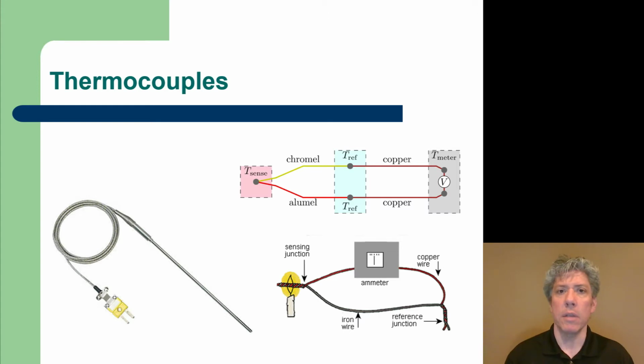At least the sensor itself is inexpensive. If you look at the upper right figure, you'll notice a chromel and alumel wire touching together. And what this represents is two dissimilar metals of the type shown there. Those are two separate alloys that are together. Now look at the lower figure and you see that there are two junctions made here with an iron wire and a copper wire. Now the place where the flame is impinging on the junction on the left, that is the sensing junction. And the junction on the right-hand side is what's called the reference junction.